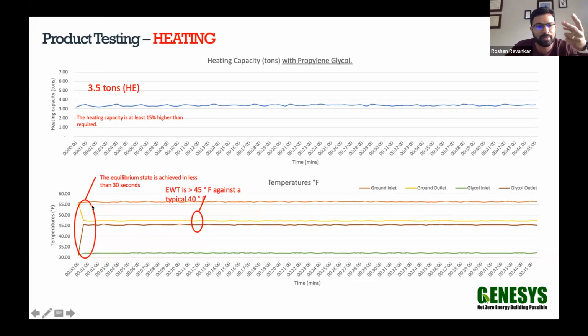Again, in this case, it's flipped because it is in heating mode. The groundwater in this case is 56 degrees. It drops down to about 48 degrees. And on the closed loop side, we supply temperatures of 30 to 33 degrees coming from the heat pump going into the CLAD. When it leaves CLAD, it is at 45 degrees. So a significant amount of temperature delta is happening at the CLAD unit itself. So your heat pump in heating mode will see a nice 45 degrees entering water temperature for this capacity from a 6-ton unit. Again, the approach, or the difference between the counterflow sides of temperatures, is very, very small.